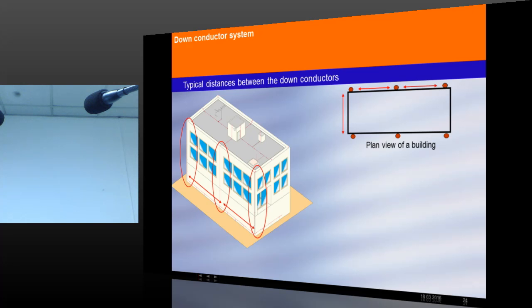See, for a particular building, at every place you see one down conductor here, the next down conductor here. In the top line of the building, this particular building has 6 down conductors. What is the purpose of having a number of down conductors? One of the prime objectives is that in a building with more down conductors, lightning current will flow through several paths. The magnetic effects of lightning are reduced. Once the magnetic effect of lightning is reduced, electronic equipment is safe.